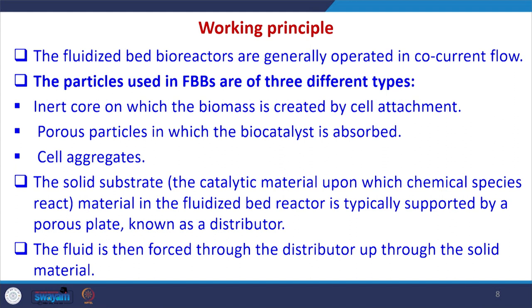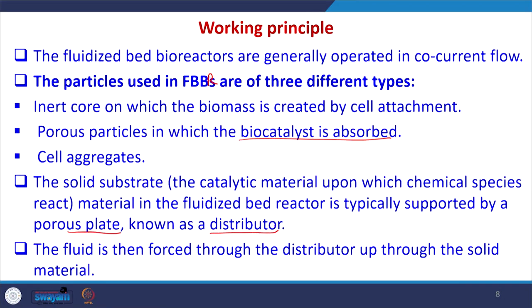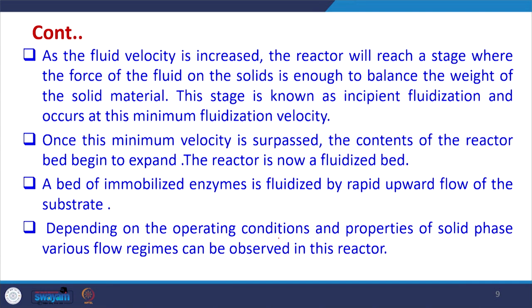The working principle of FBBR is as follows. Fluidized bed reactors are generally operated in co-current flow — the air and water both flow from the same side, which is the bottom of the reactor. The particles used in FBBR are of three types: an inert core on which biomass is created by cell attachment; porous particles in which the biocatalyst is adsorbed and cell aggregation may occur; and the solid substrate. The catalytic material in the fluidized bed reactor is typically supported by a porous plate known as the distributor, and the fluid is forced through the distributor up through the solid material.